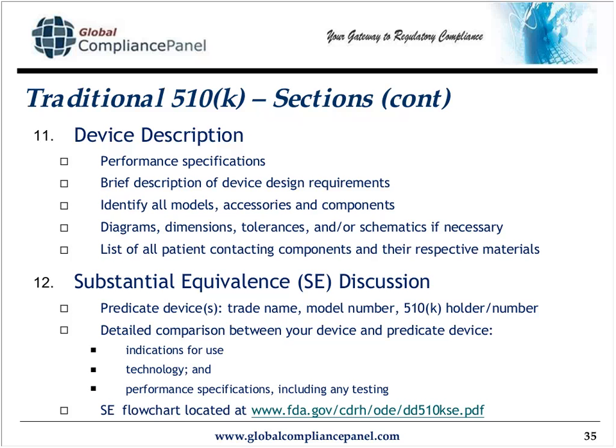Section 12 is the SE, the substantial equivalence discussion. And this is where you're going to identify your predicate device or devices, and you're going to compare your device and the predicate device using whatever characteristics you decide. I like to use indications for use and technology as much as possible. And the substantial equivalence flowchart is located at this location as well.